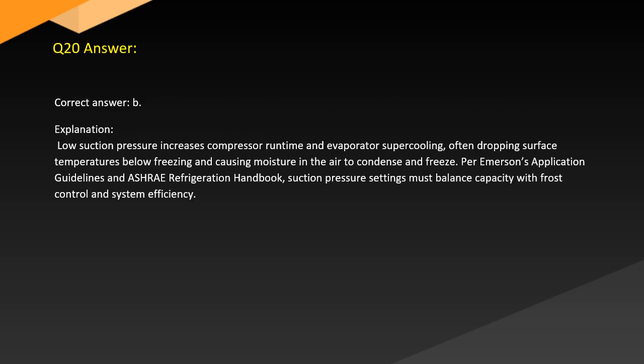Answer. Correct answer: B. Explanation. Low suction pressure increases compressor runtime and evaporator supercooling, often dropping surface temperatures below freezing and causing moisture in the air to condense and freeze. Per Emerson's application guidelines and the ASHRAE refrigeration handbook, suction pressure settings must balance capacity with frost control and system efficiency.